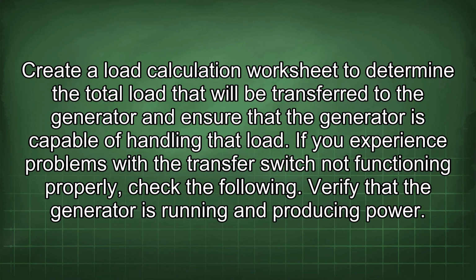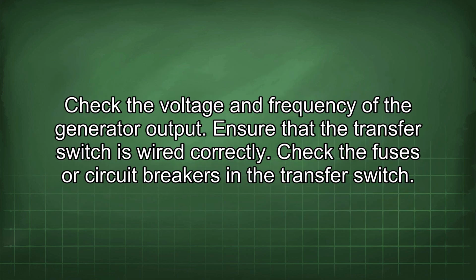If you experience problems with the transfer switch not functioning properly, check the following. Verify that the generator is running and producing power. Check the voltage and frequency of the generator output. Ensure that the transfer switch is wired correctly. Check the fuses or circuit breakers in the transfer switch.